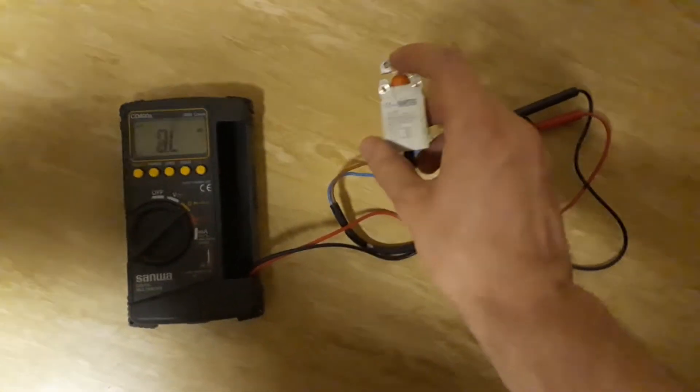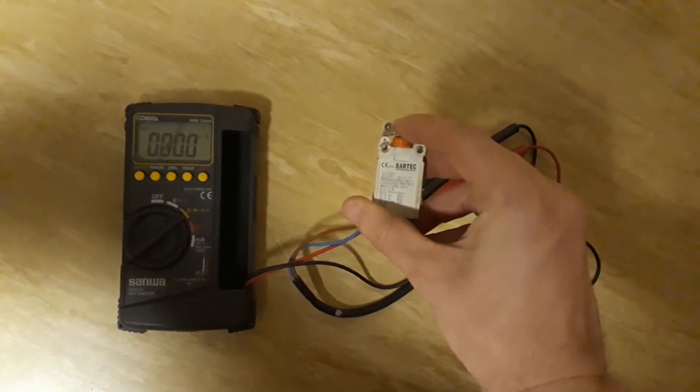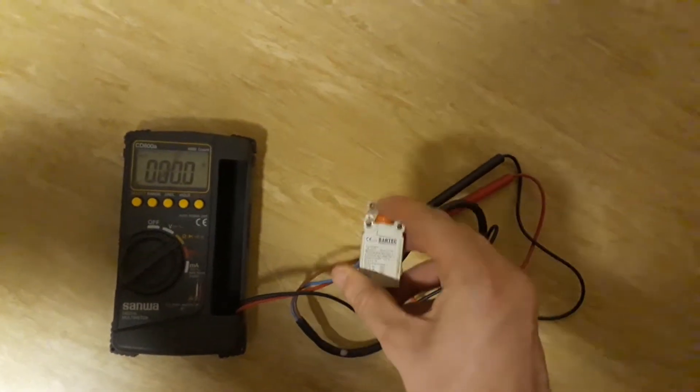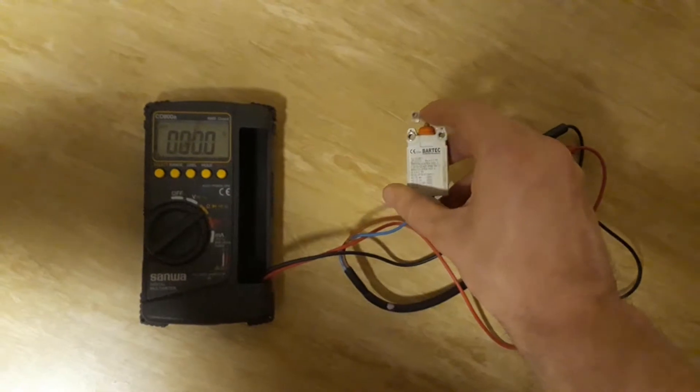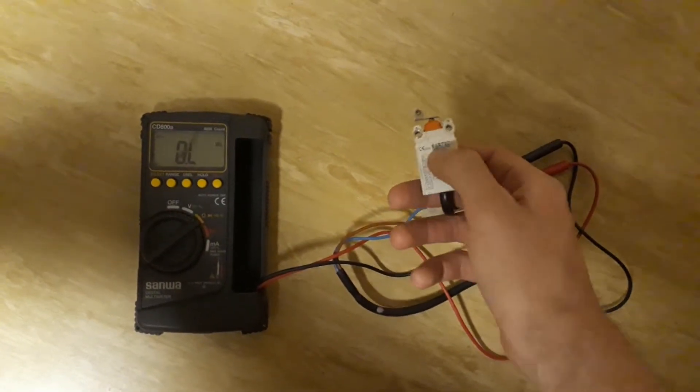It's okay, this limit switch is okay. Infinite because the contact inside is opened. Now if I interact with it, it will close and I will have zero, which is perfect.